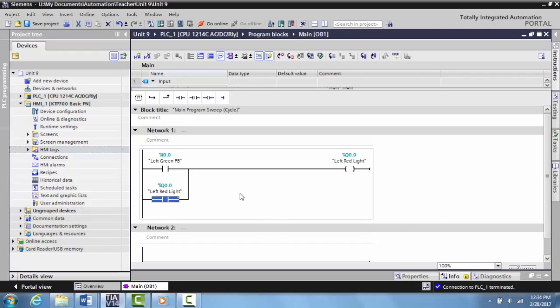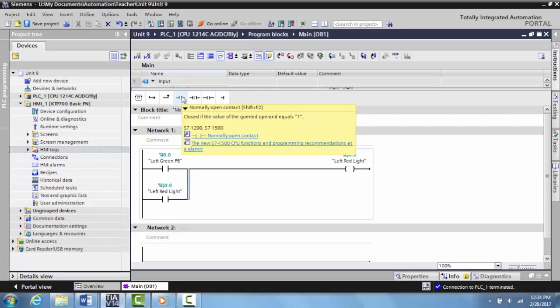Now we need a stop button. We have to have a stop button in here to turn it off or we won't have any way to turn it off. All the stop buttons should be wired normally closed.